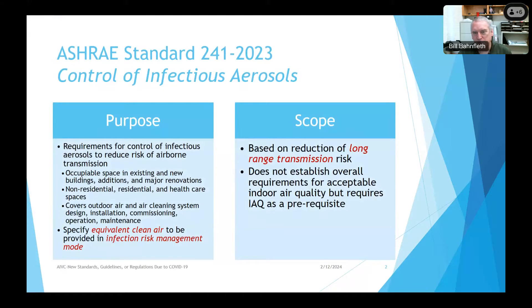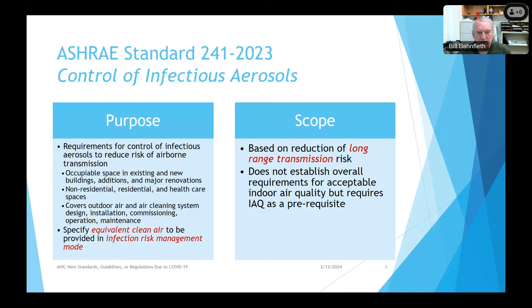The purpose and scope of the standard are the place to start. The purpose of 241 is to establish minimum requirements for controlling infectious aerosols to reduce risk of airborne transmission. It is now well accepted that airborne transmission is important not only for COVID-19, but for other diseases as well. It applies to occupiable space in all types of buildings, and not just to new buildings, but to renovations and additions. The focus is on outdoor air quantities and air cleaning system design, installation, commissioning, operation, and maintenance — so it's comprehensive in that respect, like other IAQ standards.